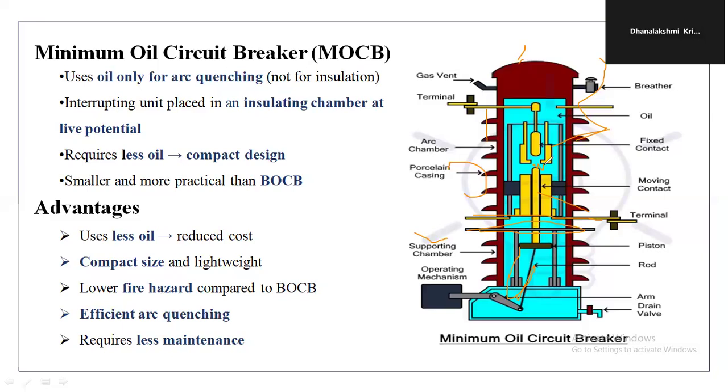This action constrains the oil to pass through the central hole in the moving contact, resulting in forcing the oil through the respective turbulator. The process of turbulation is an orderly one, in which the section or core is successively quenched by the effect of a separate stream of the oil moving across each section in turn and bearing away its gases.